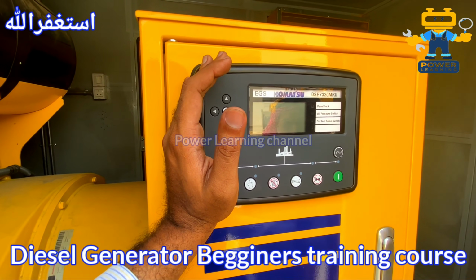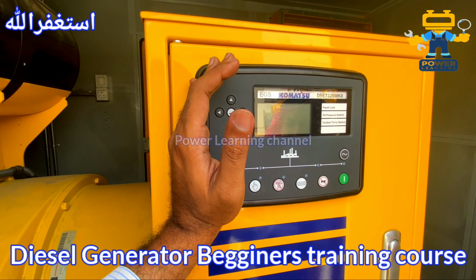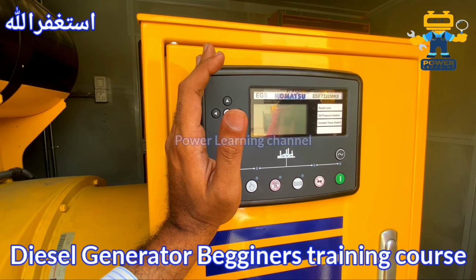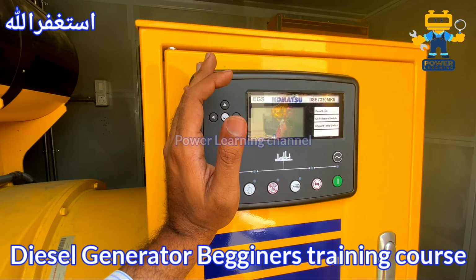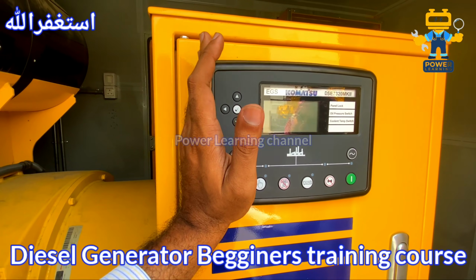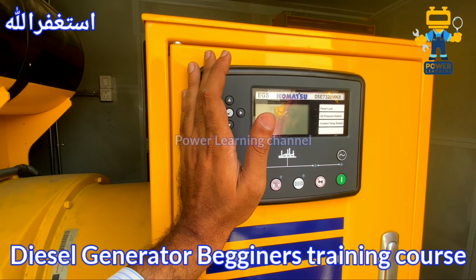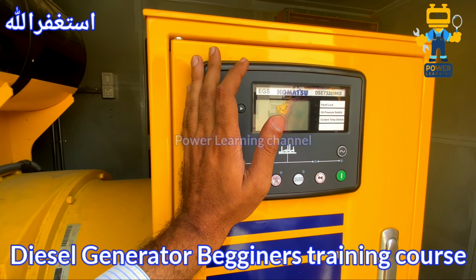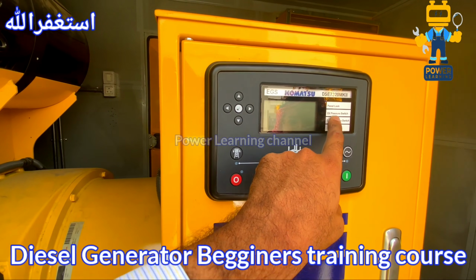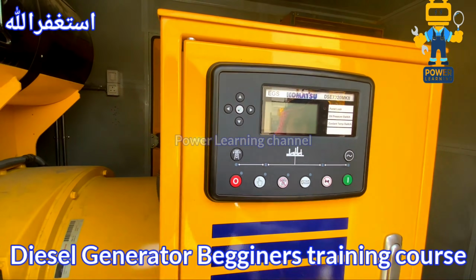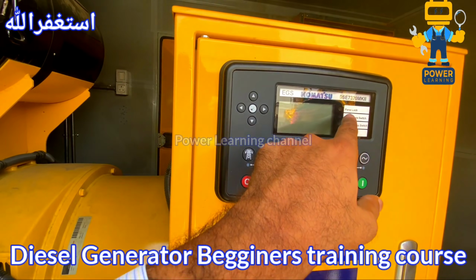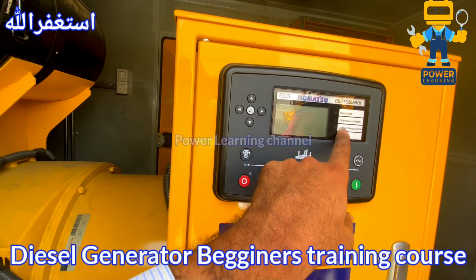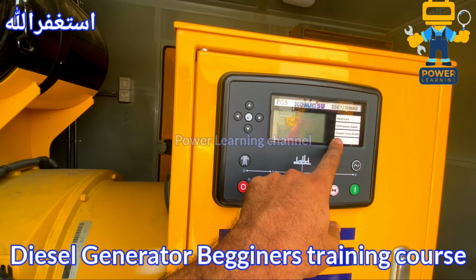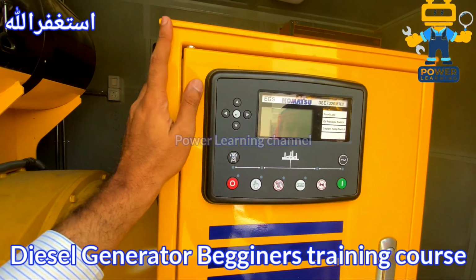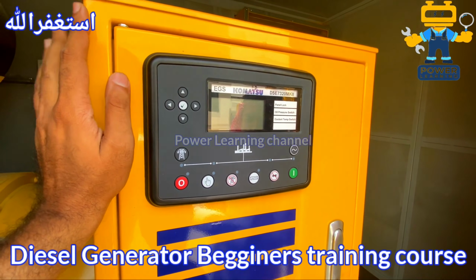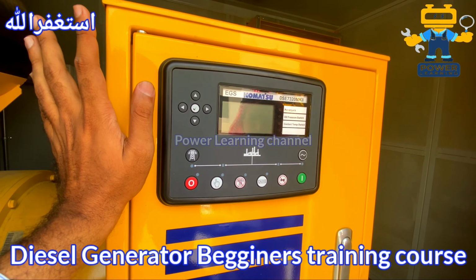If the customer puts on an overload and the set point is reached, for example, this is a 500 kVA generator. If the customer puts on 600 kVA or 550 kVA, it will trip as per the set point of the controller. Same, if the oil pressure switch gives a signal that there is no oil circulation in the engine, the engine will stop. Same with the coolant temperature switch: if the coolant is not cooling and the temperature is rising inside the engine, it will turn off. So these safeties can work automatically with this controller.